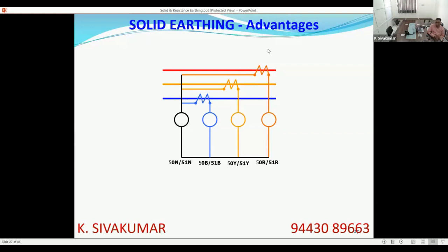Suppose you don't have an earth fault element, the earth fault sensitivity will be more than 100%, because phase fault relays are set to 100% or more. Here, if you want a finer setting, you go for a residual connected earth fault relay, where you can set as low as 10% of the CT primary rating. So better sensitive protection is also made possible here.